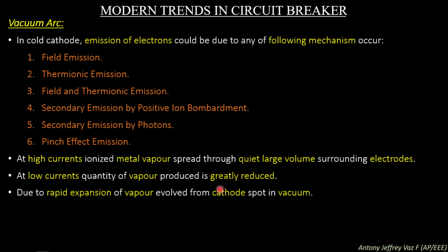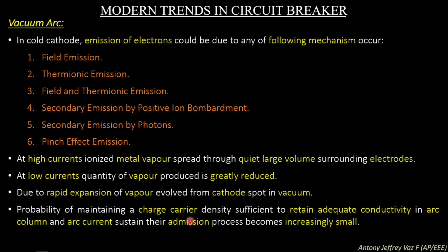is very less, due to rapid expansion of vapors evolved from the cathode spot in vacuum. So, this rapid expansion of vapors from the cathode spot into the vacuum creates a medium, and with the help of this medium, the arc is formed in vacuum. The probability of maintaining charge carrier density sufficient to retain adequate conductivity in the arc column and sustain the arc current becomes increasingly small. So, when the contacts of the circuit breaker are being separated, these microscopic projections will be converted into vapor, and this vapor should have the ability to retain adequate conductivity in the arc column.